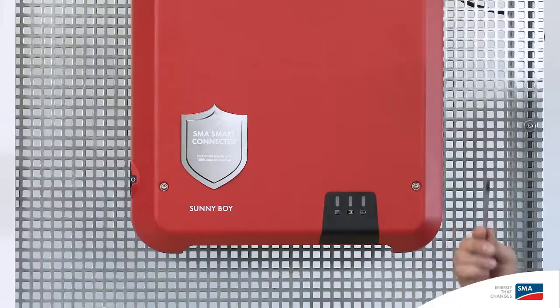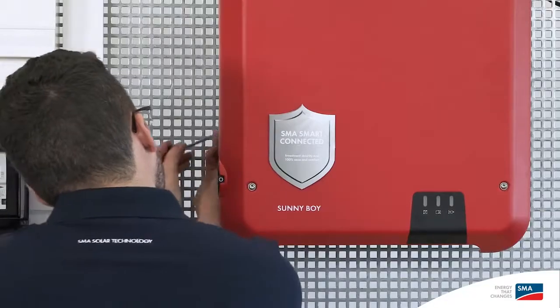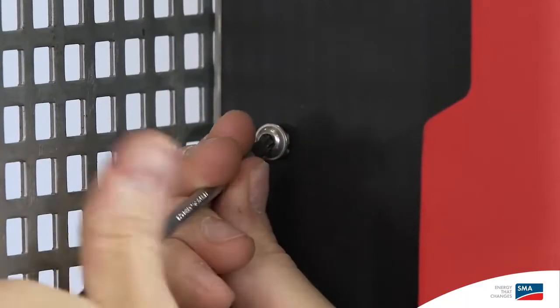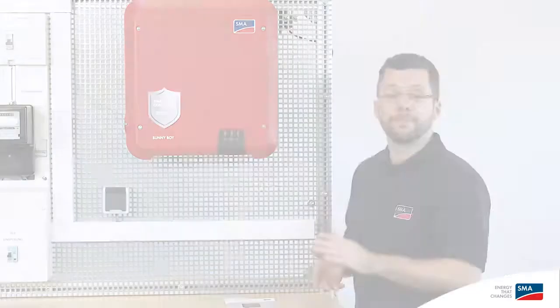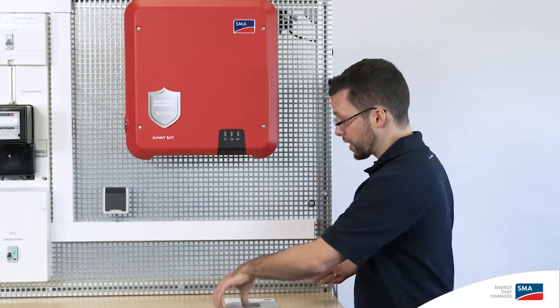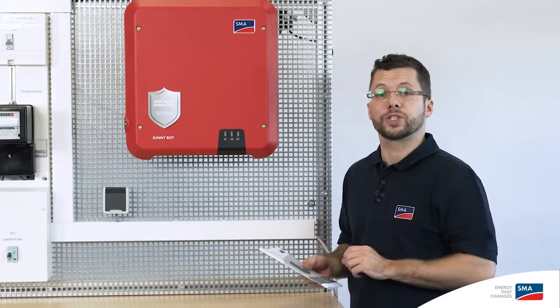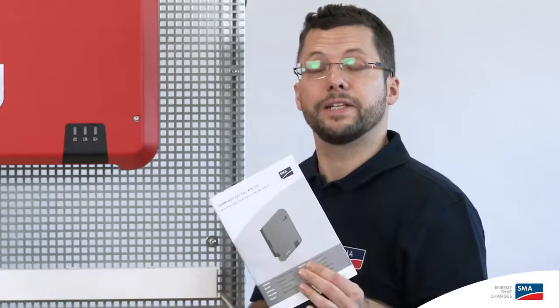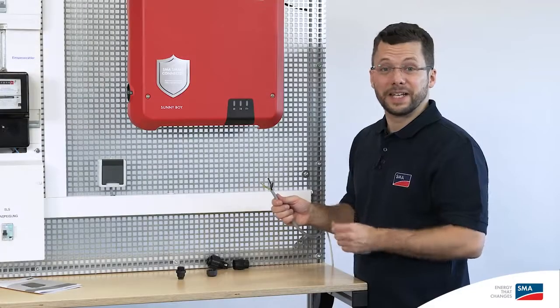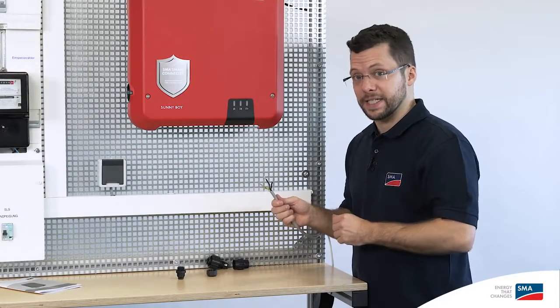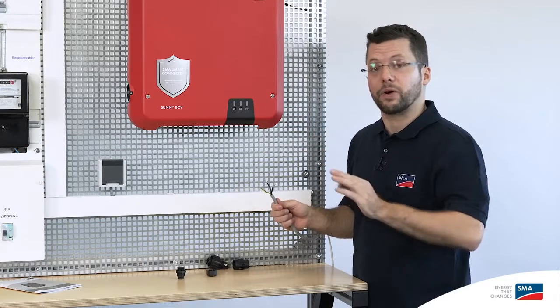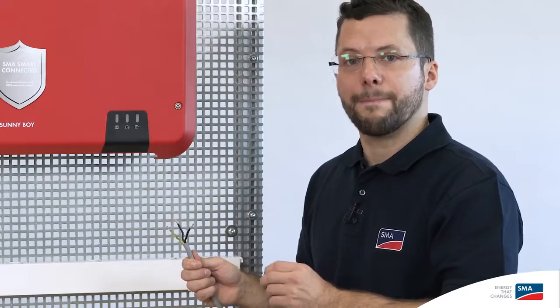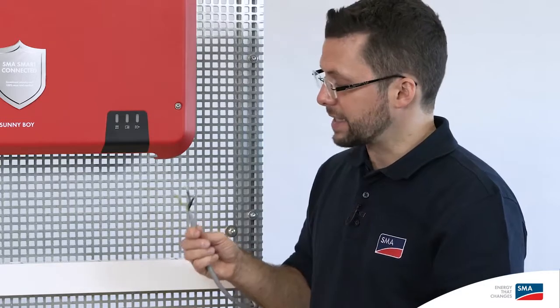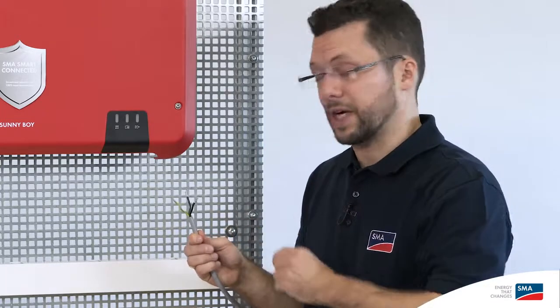After the Sunny Boy has been fixed to the wall, you should attach the anti-removal protection device. 2 screws are supplied for this purpose, which can be tightened with a Torx TX25 screwdriver. During commissioning, please observe the specified cable requirements and cable cross-sections. These can be found in the supplied quick reference guide. I'm starting commissioning of the inverter on the AC side, because then the inverter enclosure is grounded. Before assembling the AC connector, please ensure that the AC cables have been properly disconnected and are de-energized.